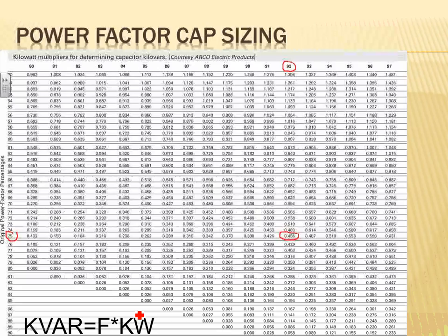Be conservative, though. Go into the lower 90s, because when the building is lightly loaded, it shifts to the other side, unless you have an adjustable capacitor where it can sense the voltage, like utilities do. It senses what the power factor is and turns things on and off. Basically, it's dynamic. It adds or reduces from this bank of capacitors. But the cheapest way is just a box right by the switchgear, tie it to your system, up your power factor to say 92. When it's lightly loaded, it shifts to 97 or maybe 100, but it doesn't shift to the other side into the leading part. Any comments about these?